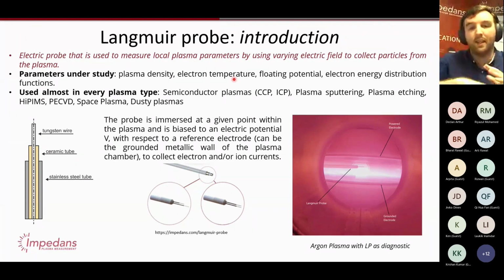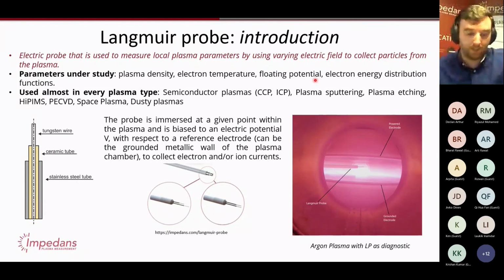In reality, the electrons have a distribution of energies, but we usually boil that down to one number, which is the electron temperature. It also measures the floating potential, which is important if you have a substrate inside the system which is floating. You can use that to work out how high in energy the ions will bombard that surface. Also, you can measure what's called the plasma potential, which is basically what voltage the plasma is at with respect to the chamber ground. Also good for giving information about ion impacts, and so on.